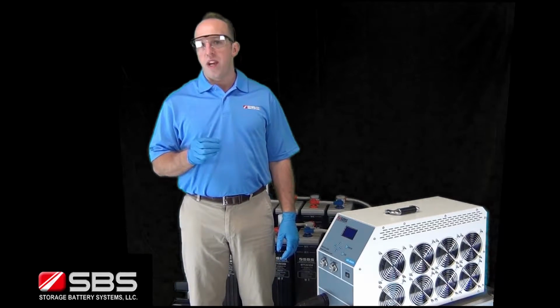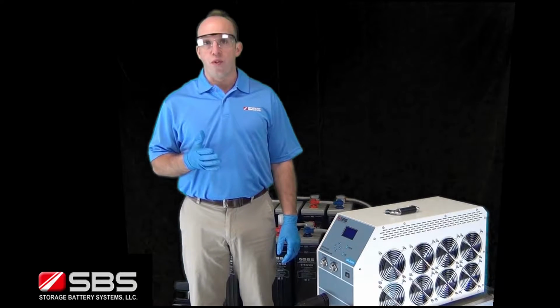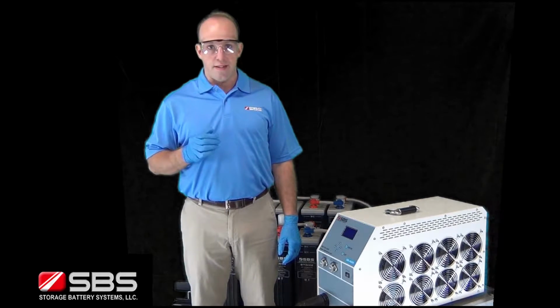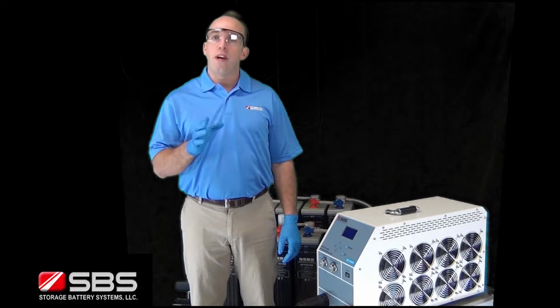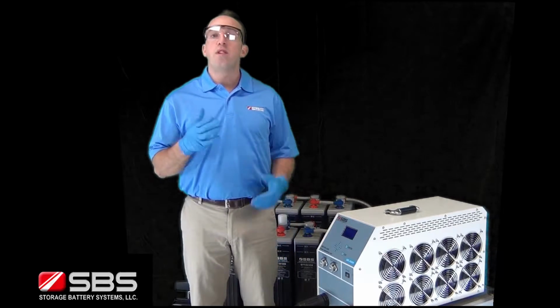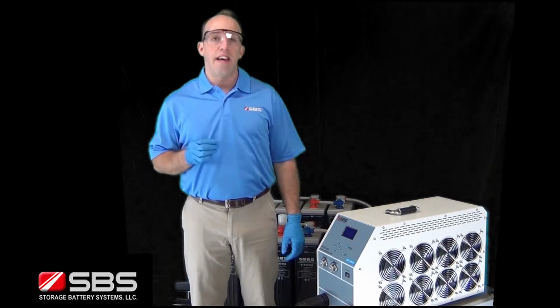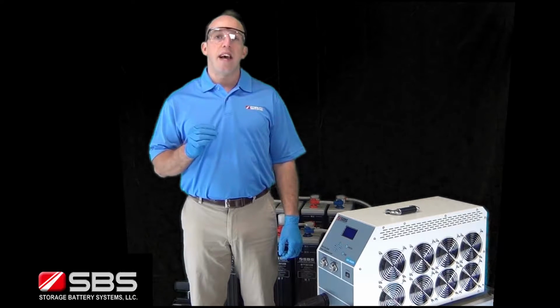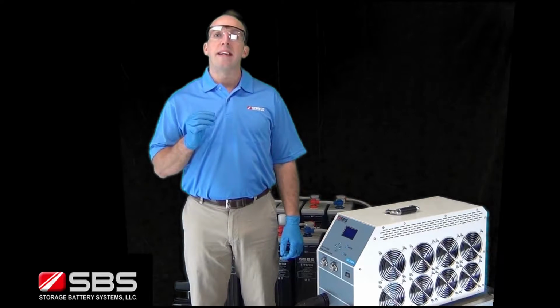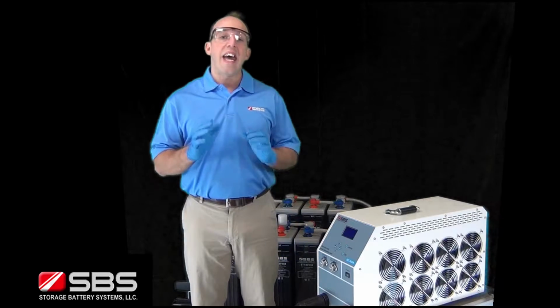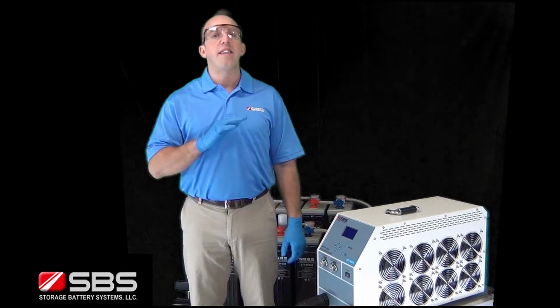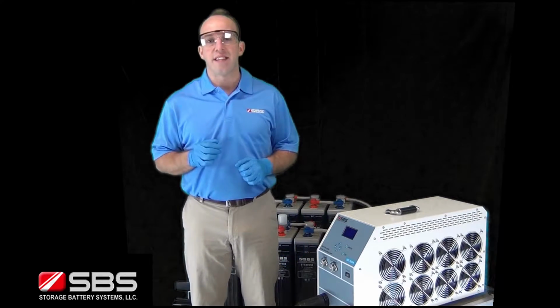Load bank testing is a way of verifying the correct operational performance and capacity of the battery system. Load bank testing is required for NERC compliance, which applies to organizations that connect to the national grid. The SBS S-Series load banks allow you to maintain compliance with NERC and IEEE standards, making them an ideal solution for your battery testing needs.